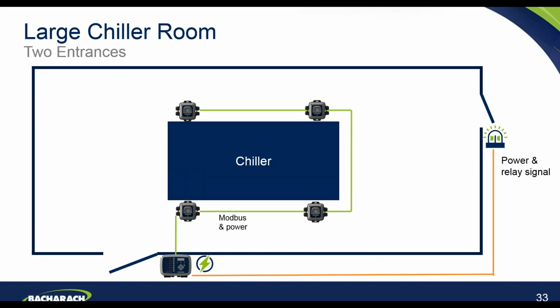Next example is a large chiller room. In this example, we have an MGS-400 control panel just outside one of the entrances to the room with power into that control panel. So that provides your audible and visual notification outside that entrance of any alarm conditions. Inside the room here, we have 4 MGS-400 units. Again, they're providing detection and audible and visual alarms in the event of an alarm condition. You'll notice on the right-hand side here that we also have a second entrance into this particular room. And so from that control panel, we're also using power to drive a second audible and visual notification which sits outside that second entrance to the room.